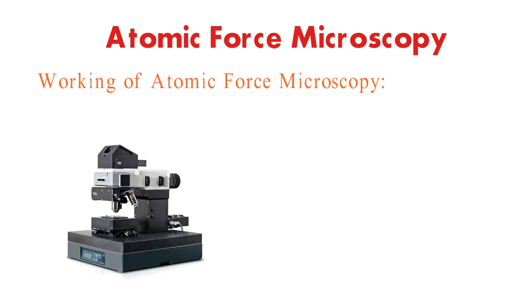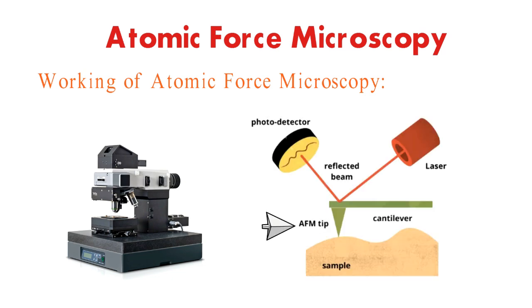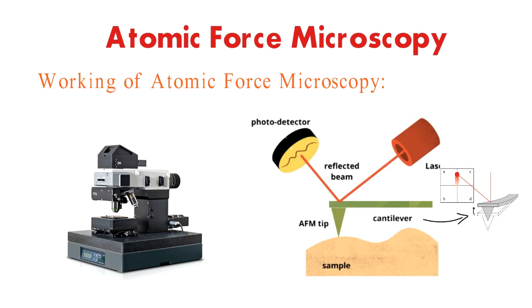The principle behind AFM is quite remarkable. It utilizes a sharp tip attached to a flexible cantilever. As this tip hovers just above the sample's surface, forces between the atoms in the tip and the atoms on the sample interact. These forces cause the cantilever to bend, and the deflection is measured by a laser system, providing real-time feedback. The result? A detailed 3D map of the surface's topography, atom by atom.